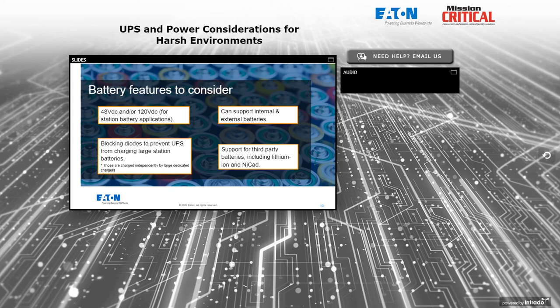It's also common to see blocking diodes in an industrial UPS. That's the case where the UPS is connected to a large station battery, and the user does not intend for a small UPS to be charging that big battery. So the blocking diodes are placed in the DC circuit of the UPS to allow the battery to discharge into the UPS to be converted to AC during a power outage, but it does not allow the UPS to push power back onto that battery. In other words, it doesn't allow the UPS to charge the battery. That's handled by other charging stations that are part of the building electronics that support that battery. So diodes are like a one-way valve there that allow the battery to discharge into the UPS, but it blocks that UPS from charging a big external battery.